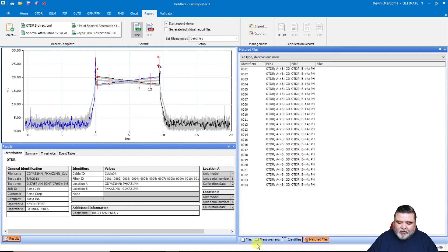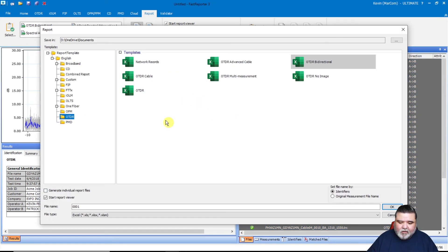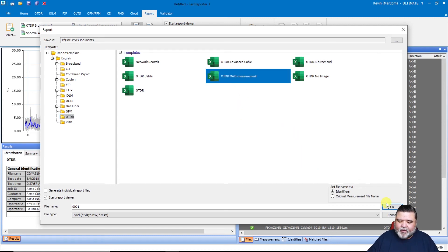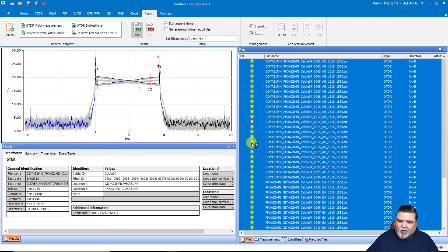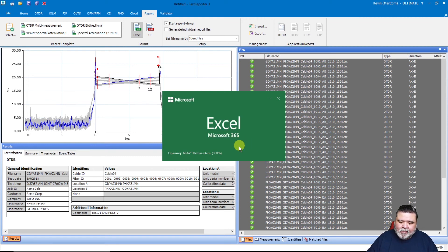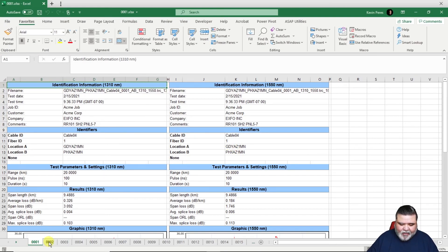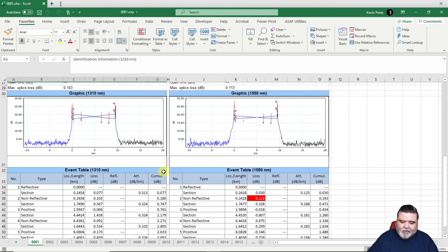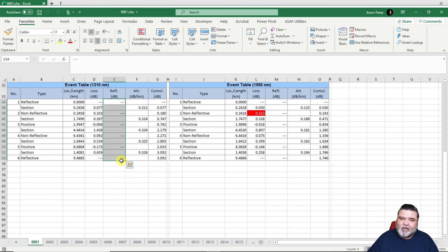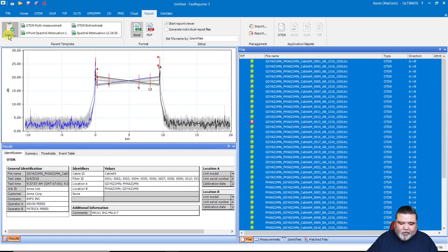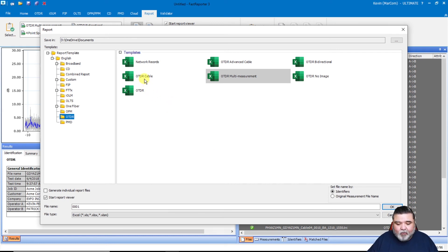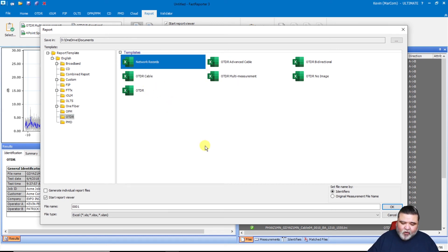There are a lot of different reports available. Multi-measurements is a nice one I like as well — it's primarily bi-directional so you won't see reflections. This is really good for looking at splice loss in a nice clean format. You get individual tabs — 24 tabs here — with 1310 on the left and 1550 on the right showing all the information. You won't get reflection because reflection is not bi-directional — it's only in one direction. There are also individual OTDR reports, cable reports, and network record reports. I encourage you to go through all of those.